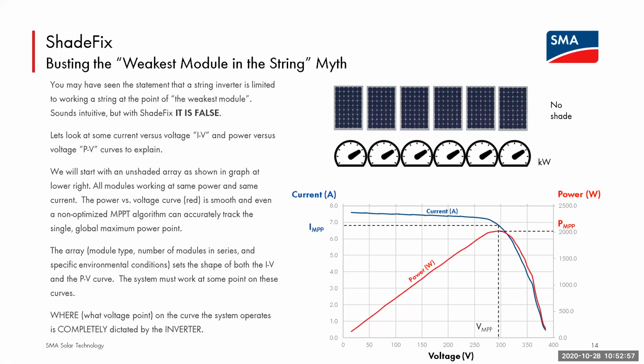That is basically false. So now you know when you put a string of modules together, that's creating an IV curve, that's creating a power curve, and depending on what that curve looks like, the SMA inverter can always choose a maximum point in which it can pull power off that curve, even if there's shade on certain modules at certain times and other modules during other times. So we'll start here again with an unshaded array. These speedometers represent the power output of each of these modules in a non-shaded condition. You can see everything's at full power or full speed, and this is where the curve is. The inverter is choosing to pull power at this inflection point here, basically the highest voltage and highest current level, which is the highest power.